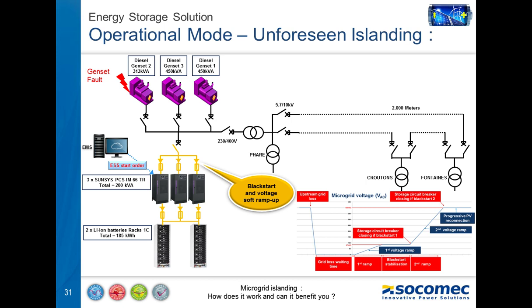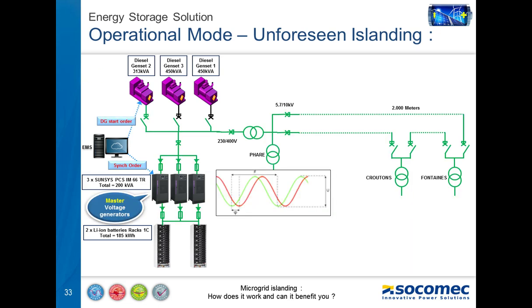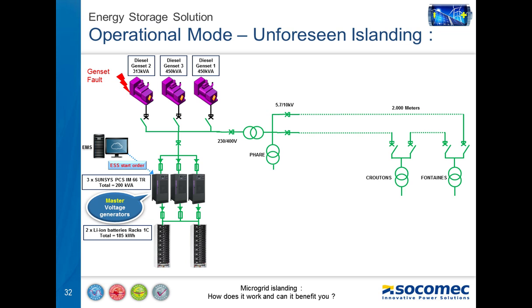For the second situation, for motor load, we are able to close the circuit breaker when the voltage between each PCS reaches 80 volts. In this case, we close the circuit breaker and we increase progressively, step by step, the voltage in order to reach progressively the nominal voltage. This solution allows to avoid any inrush current on the installation. At this moment, the energy storage system automatically ensures the balance between the local production and the consumption, while the state of charge and the power of the PCS are within the operating range.